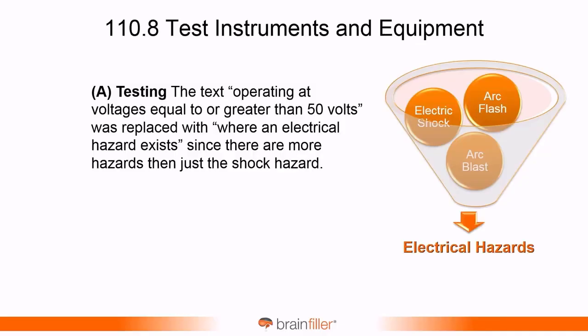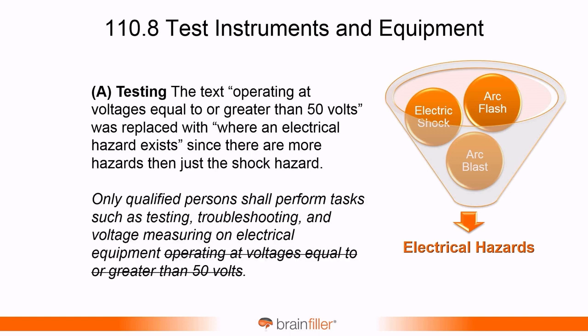Test instruments and equipment. So with test instruments and equipment, a minor change here, but it actually has, I think, some far-reaching ramifications. The text "operating at voltages equal to or greater than 50 volts" was replaced with "where the electrical hazard exists." And let me show you what this actually looks like, the full text. The reference to 50 volts was eliminated. The reason the reference to 50 volts was eliminated, that kind of implies that the only real issue is the shock hazard. And there's more than a shock hazard.